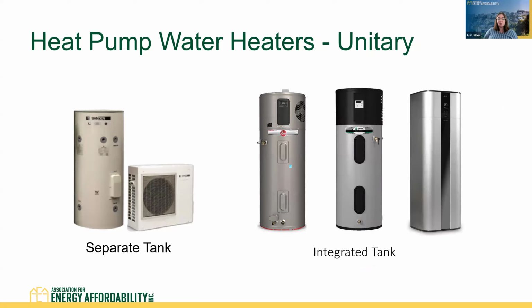Unitary heat pump water heaters. This is a one-to-one equipment to dwelling unit. Here we've got both integrated or packaged tank options and separate tank or split options. The integrated tank looks similar to a storage gas water heater, but there's actually a heat pump in there. For the separate tank option, we've got a smaller capacity heat pump compressor paired with a storage tank. There's only one manufacturer I know of offering a split system at the scale for a single dwelling unit, and that's Eco2, which creates the Sanden system, pictured there.